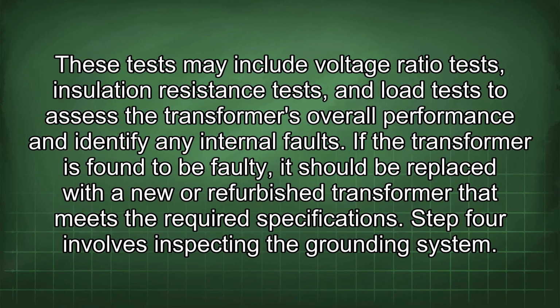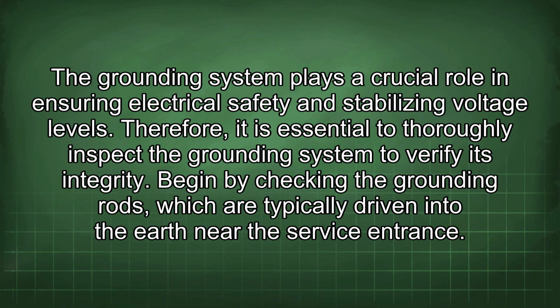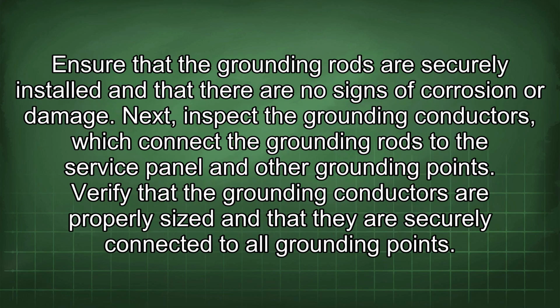Step 4 involves inspecting the grounding system. The grounding system plays a crucial role in ensuring electrical safety and stabilizing voltage levels. Therefore, it is essential to thoroughly inspect the grounding system to verify its integrity. Begin by checking the grounding rods, which are typically driven into the earth near the service entrance. Ensure that the grounding rods are securely installed and that there are no signs of corrosion or damage.